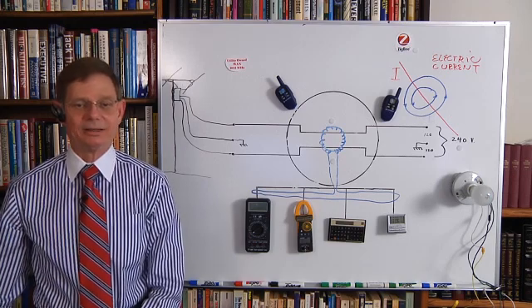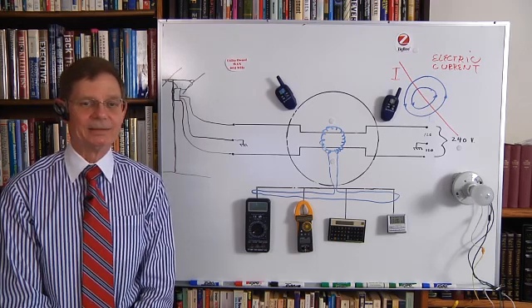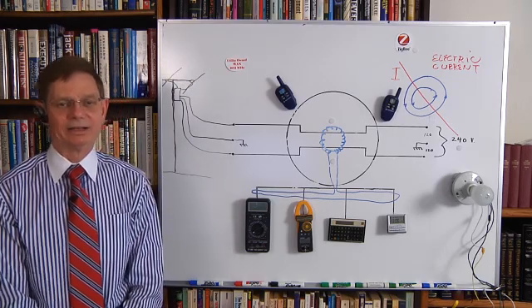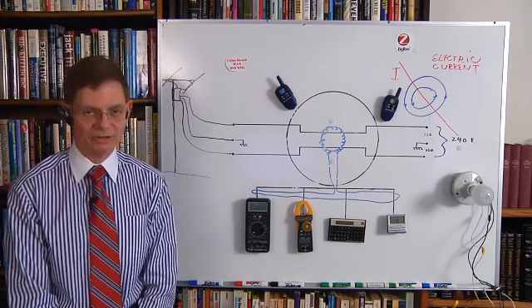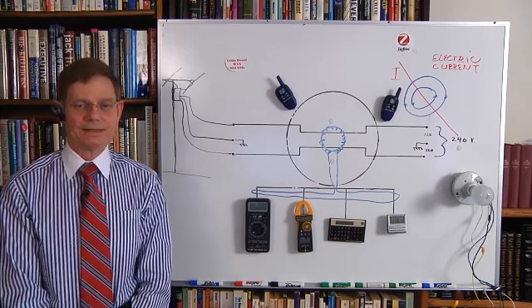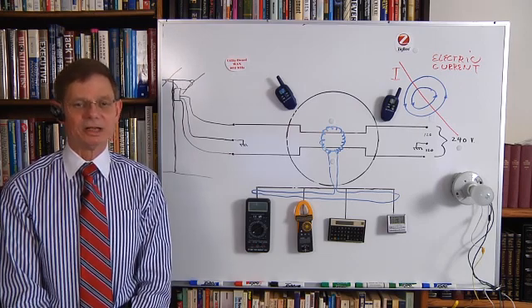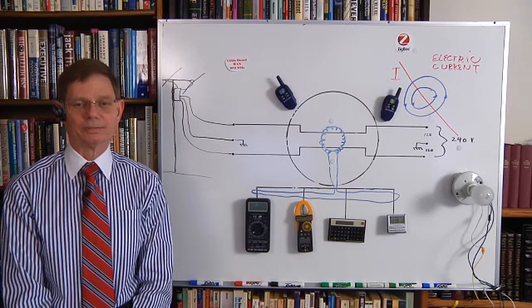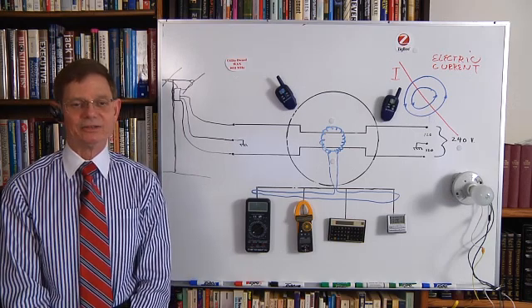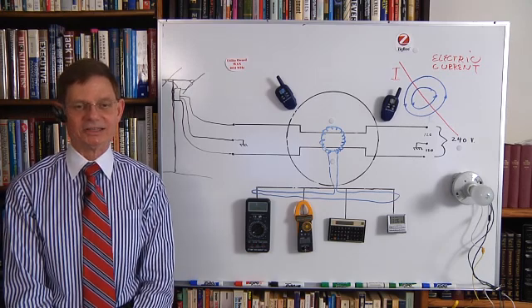Whereas a utility company may have a meter programmed to send lots of data to the utility, say at a periodic frequency of every 10 to 15 minutes, most of the mathematical calculations for advanced rates such as time of use and demand rates can be performed inside the meter or in the building. Thus, the need for frequent communications can be eliminated. Since most of the new smart meters allow for the utility to remotely program the meter's operating system, the utility can change the data transmission schedules from, say, every 10 to 15 minutes to, say, twice a month.